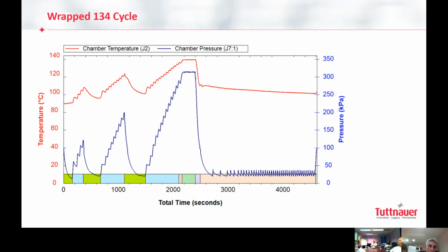Condition one, air removal. We are not able to remove because it's a gravity, and we remove between 90 to 95%. It means we stayed with 5 to 10% of air. So we are not complying in this class S, Easy Plus. And when we come to the drying, yes, we comply. So one of the two conditions is okay, confirmed. That's why we are categorizing it as a class S. Questions to this moment? No, actually, it's very informative.